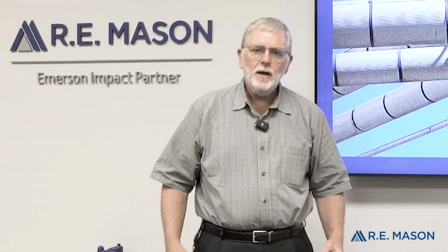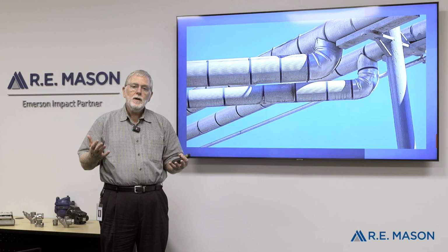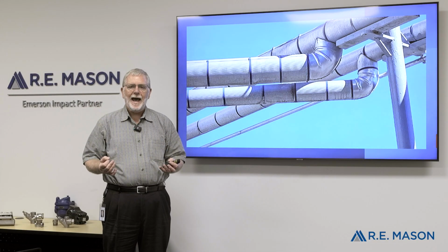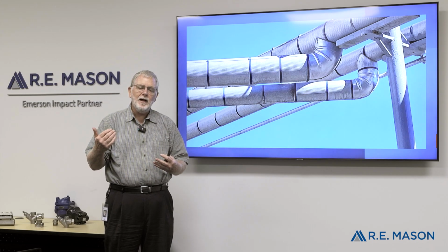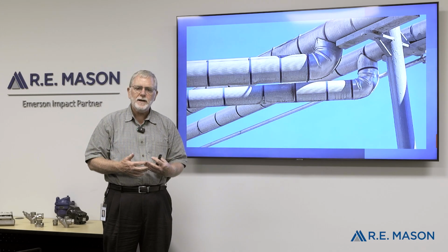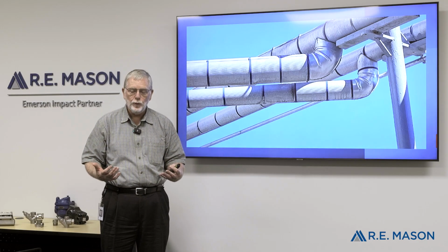Other things that we look for to help you understand is, here is where we're taking steam off the steam line and putting condensate back into the steam. And if you notice on these, they're both off the bottom. They should both be on the top. Why? For steam, coming off the top, you get the majority of the gas and you don't get liquids. Here, it becomes more like a drip leg, and everything that's in that condensate line is falling in, going into your process, which deteriorates the heat transfer of what you're trying to do.